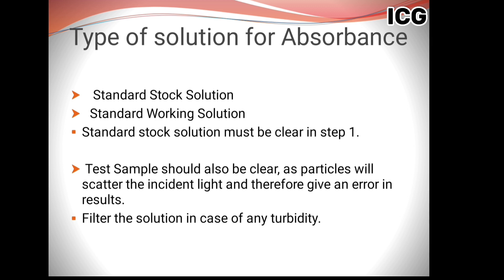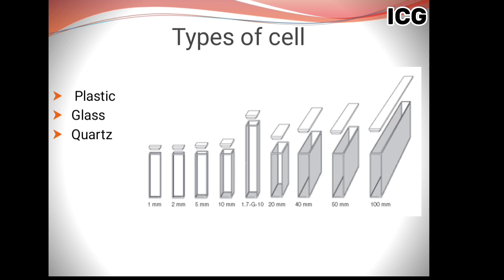Regarding types of cells, normally in the market you have plastic, glass, or quartz — three different types available. It depends on which ones you have and which are required according to your instrument and your test. However, both cells — the one for the sample and the one for the standard — should be the same type, since you are comparing sample and standard at the same time.